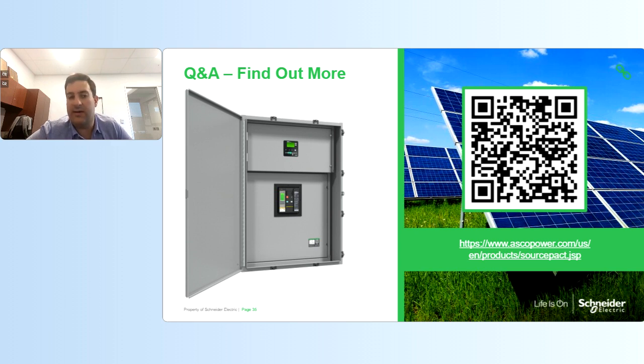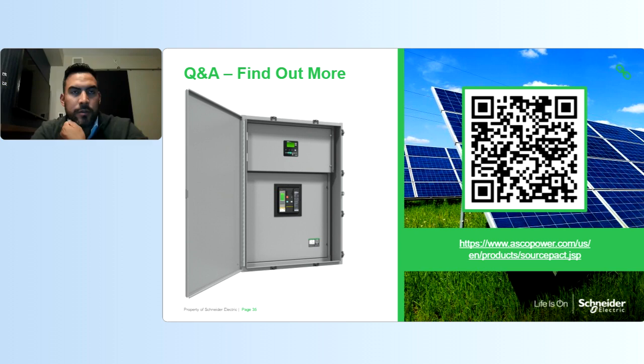to provide the isolation and the paralleling connection to the utility when you're operating and everything's okay and you want to be grid tied, or when power goes out and you want to open up and be isolated so that you can power your critical loads on that branch. So I think Benny covered that, and when the presentation goes out, you'll see all those excerpts that were referenced by Benny. Yeah, correct. And that's 700.12 in the National Electric Code. So once you download the copy of the presentation, you can reference that.